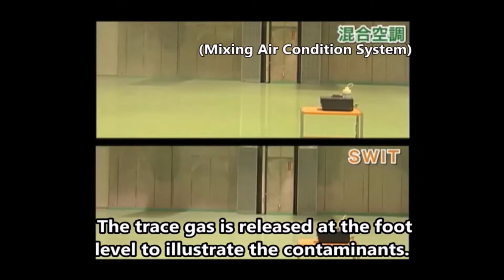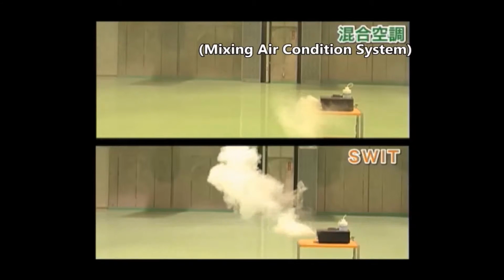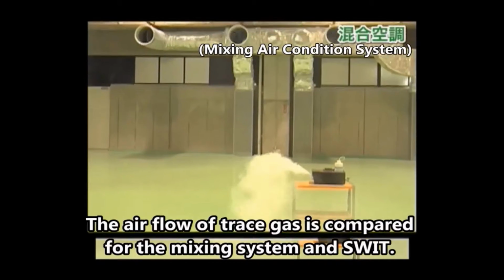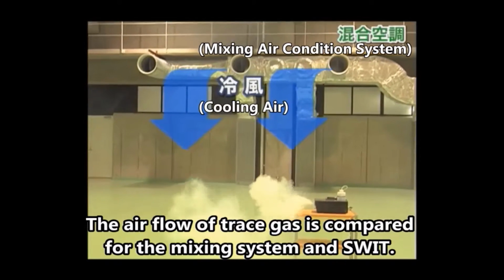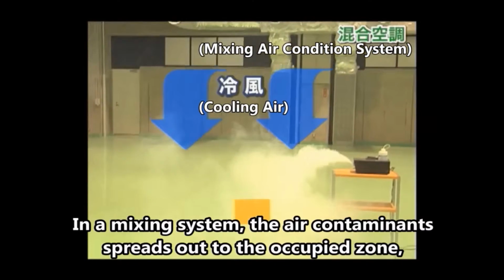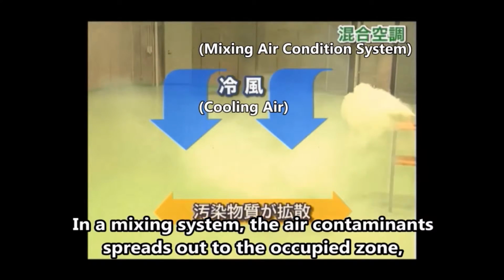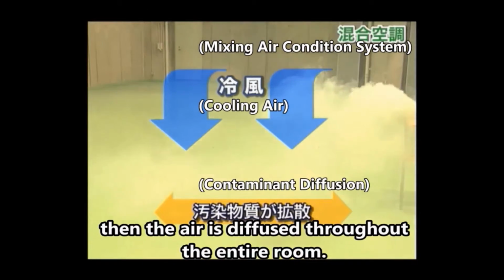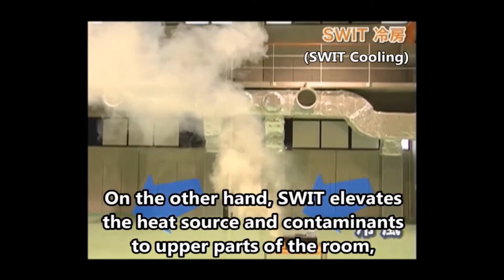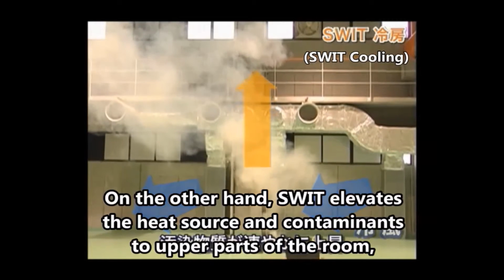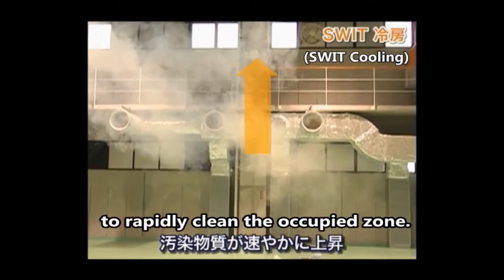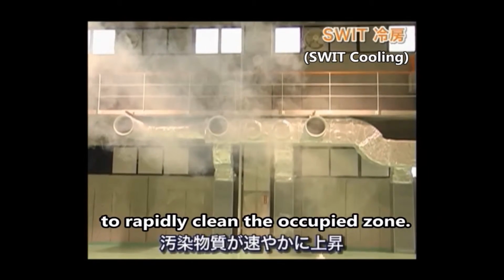The trace gas is released at the foot level to illustrate the contaminants. The airflow of trace gas is compared for the mixing system and Swit. In the mixing system, the air is diffused throughout the entire room. On the other hand, Swit elevates the heat source and contaminants to upper parts of the room to rapidly clean the occupied zone.